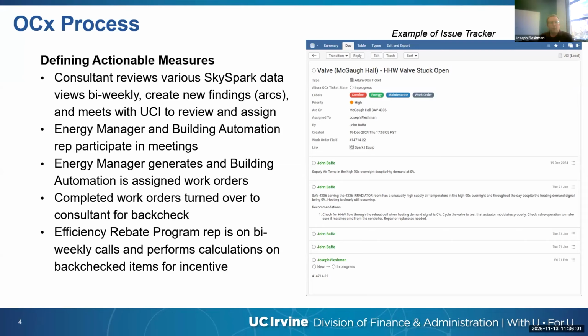And involved in those biweekly meetings, we do include our energy efficiency rebate program representative, so that we're feeding them live data of, this has been fixed, this has been fixed, this has been fixed, and then they can perform calculations on the back checked items for incentives. So on the right here, we have an example of sort of an issue tracker. There's a heating hot water valve stuck open, when it was identified, what the evidence is. And through SkySpark, you can actually click through and go straight to the graph that shows this abnormal behavior. So I can validate it, my team can validate it, and know exactly what they're looking for.